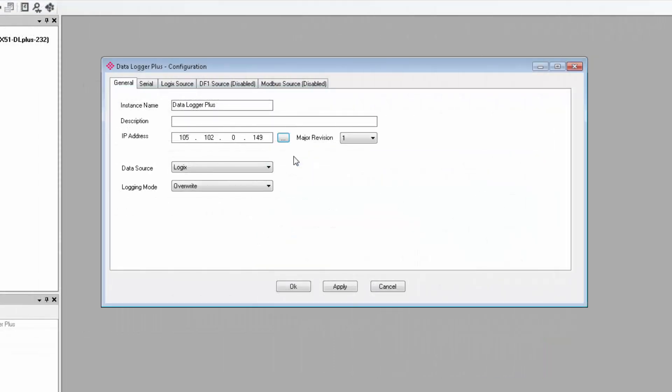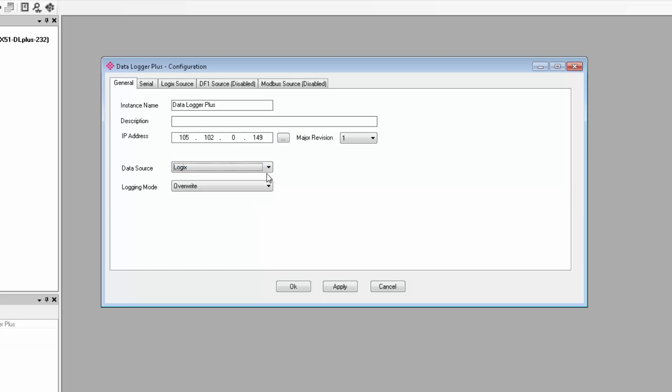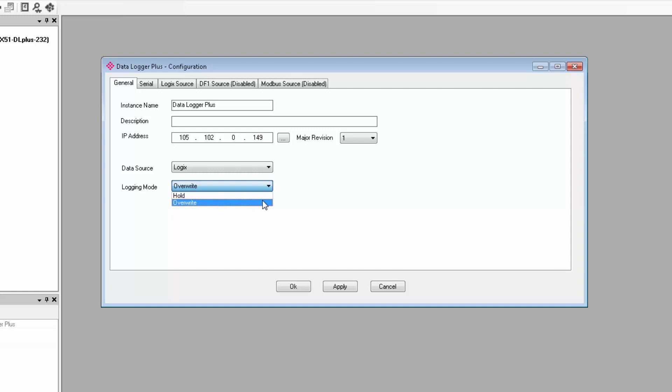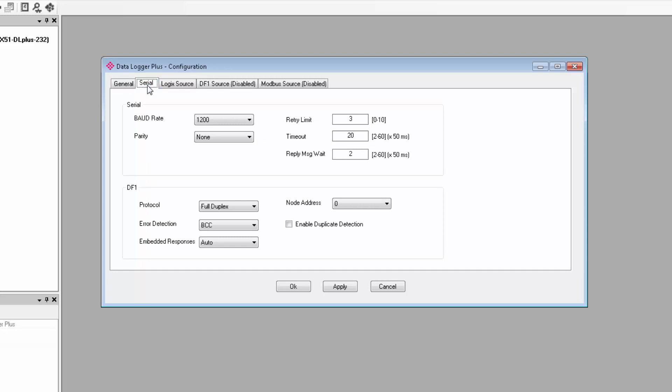Next, we come to the data source selector. From the drop-down menu, we can select what sort of device that we want to log data from: a Logix controller, a DF1 device, or a Modbus RTU or TCP IP device. For this training session, I'm going to log data from a CompactLogix controller, so I'll select Logix. We also have two logging modes, Hold and Overwrite. You're basically selecting what you want the PLX51 to do in the event that its database of more than 16,700,000 tags fills up. Hold tells it to stop logging new data and just hold on to what it has until the records are downloaded and cleared. Overwrite will instruct it to go back and begin overwriting the oldest logged data with new data. For this demo, I'll select Overwrite.